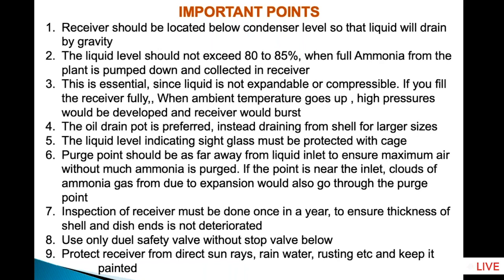But if you at all want to use a stop valve, many customers insist, no, no, no, we want to use a stop valve. Then do one thing: keep the valve fully open, remove the handle, and that handle should be kept under lock and key with the manager so that nobody accidentally closes this valve. This also protects the receiver directly from sun rays, rainwater, etc. If you are keeping the receiver outdoors, many people keep the receiver outdoors near the evaporative condenser on the terrace or outside the machine room in the plant room.